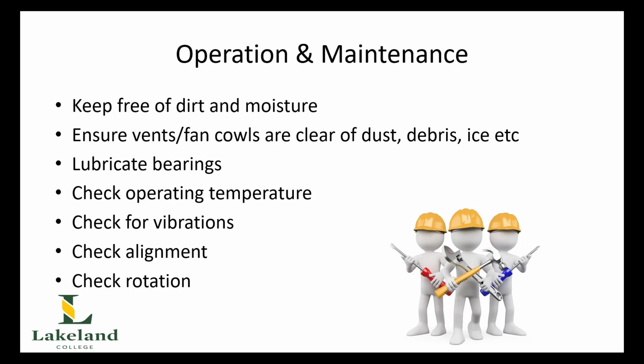They have to be perfectly in line, because if not, there's a lot of wear and tear placed on the shaft and we can end up shearing off the coupling. And then finally, we need to check the rotation. And that's certainly something we can do as well. We can make sure these things are rotating in the right direction, as indicated by the arrow on the motor frame. And again, if it's a 3-phase motor and we wish to change rotation, the electrician can swap any 2 phases.